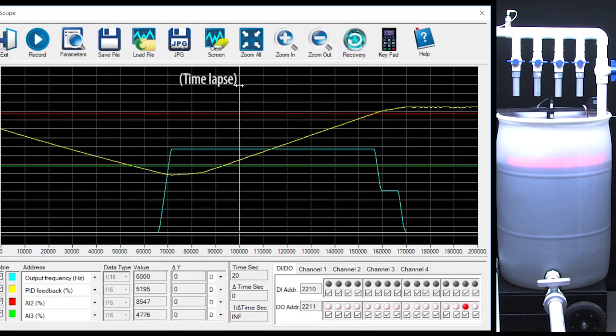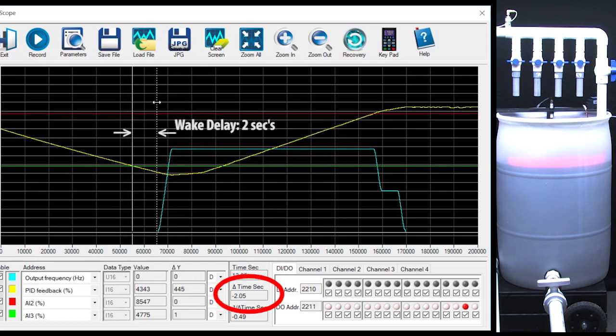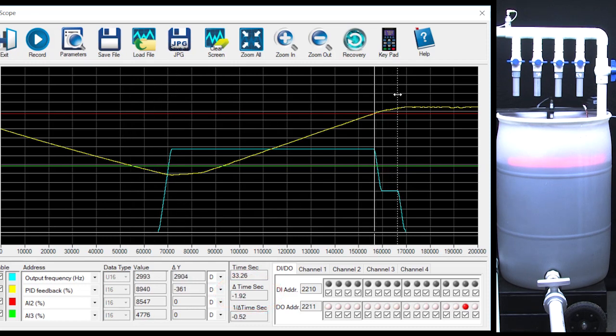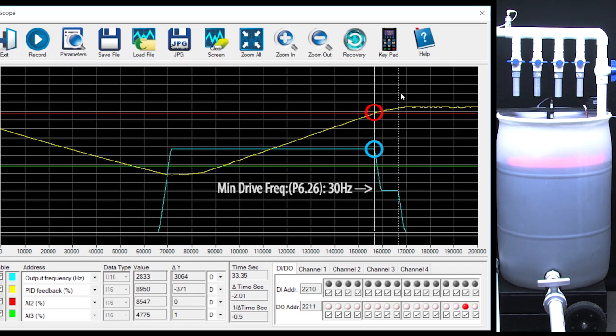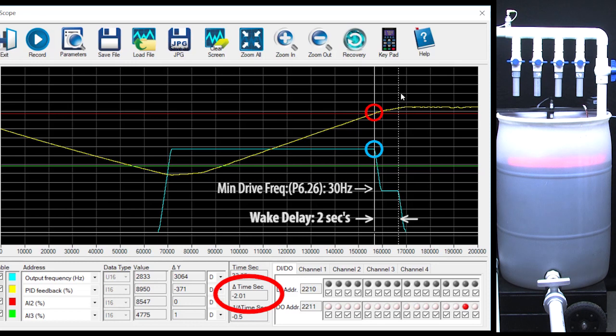Hit run and sure enough, wake up was delayed by 2 seconds and uh oh, what happened here? Well sleep kicked in immediately, but it held at this minimum drive speed while it waited for the 2 second delay before shutting down.